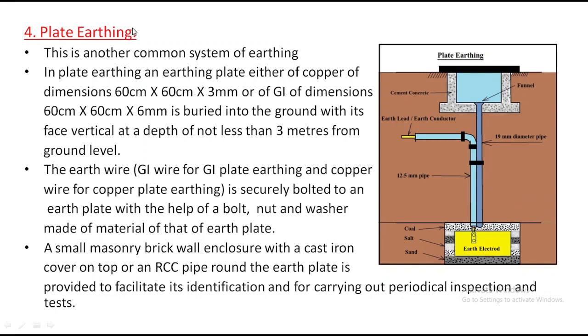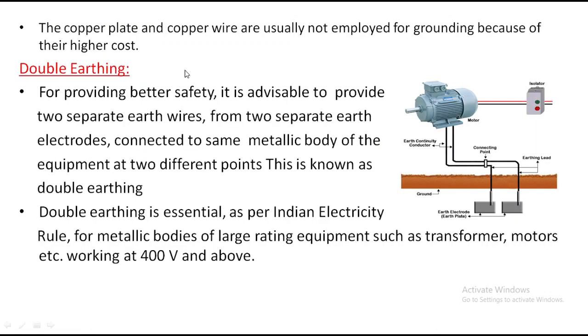Plate earthing is simply a plate. Don't confuse here: at this point the conductor will be connected, and the leakage current will flow from this point. This pipe is only for testing. The copper plate and copper wire are usually not employed for grounding because of the higher cost. Generally we do not prefer copper, because its cost is very high.